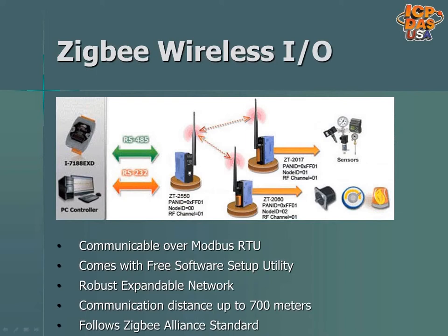ZigBee is a wireless specification that operates over the 2.4 GHz band. It was designed to create personal area networks with low data rates and uses small, low powered radios. ZigBee devices are set up with a free software utility and can communicate up to 700 meters. Our devices follow the ZigBee Alliance standard so they can be used with other vendor devices that also follow the ZigBee Alliance standard. Our ZigBee products support Modbus RTU communication. With ZigBee communication, the converters act as a repeater and repeat the signal onto the next node in the network.